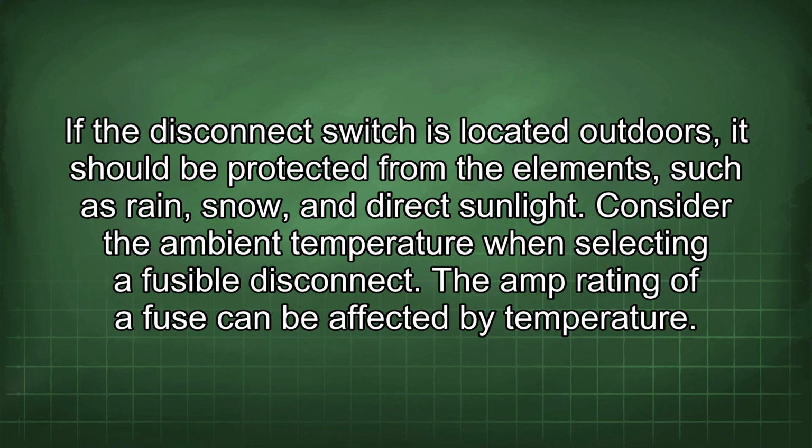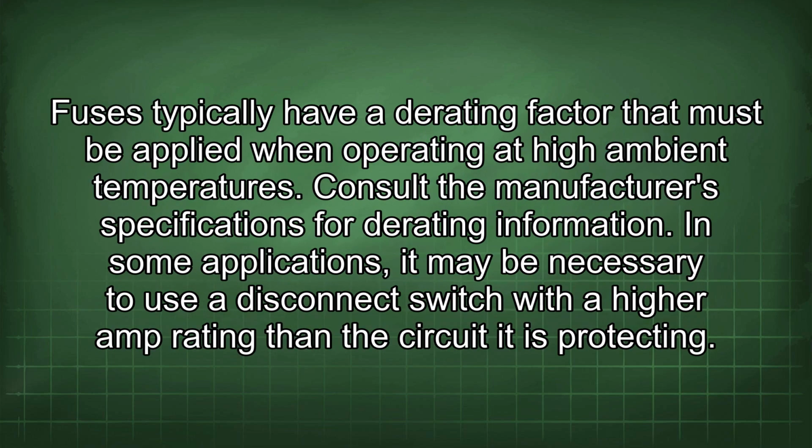Consider the ambient temperature when selecting a fusible disconnect. The amp rating of a fuse can be affected by temperature. Fuses typically have a derating factor that must be applied when operating at high ambient temperatures. Consult the manufacturer's specifications for derating information.